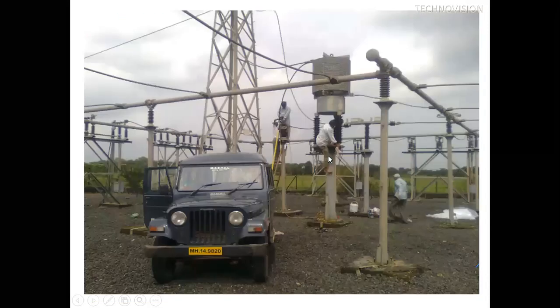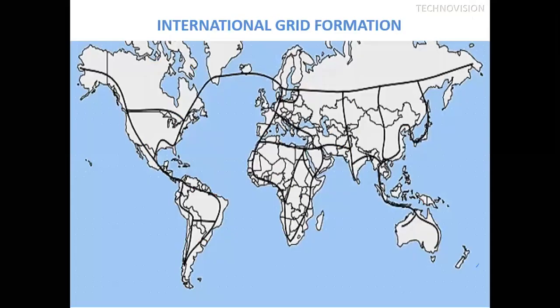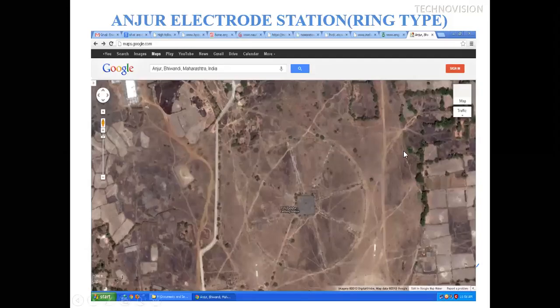And if you see the structure or nature of the earth, when you go deeper and deeper into the earth towards the core, the resistance decreases. So whenever this current goes into the earth, it goes deeper and deeper. So in DC transmission monopolar ground return mode, current flows from the inverter to the rectifier and completes its path. So this is like this.